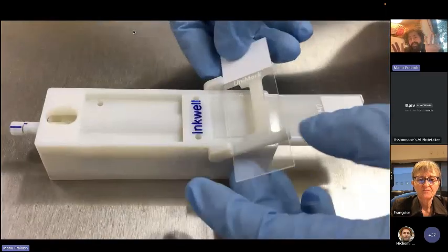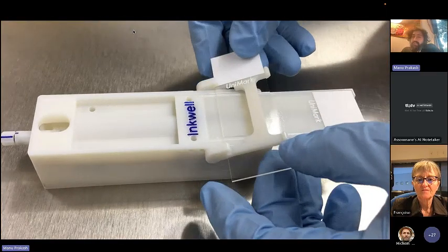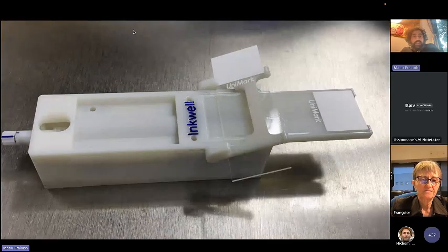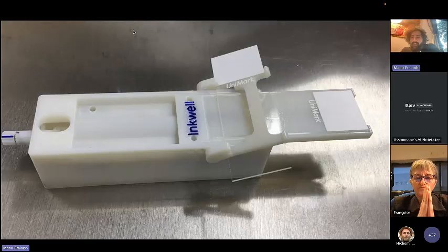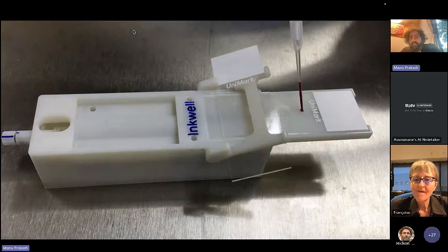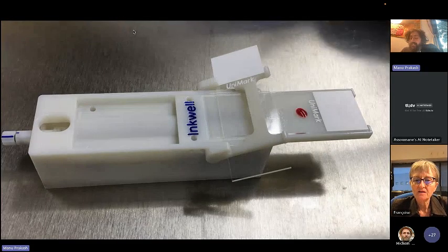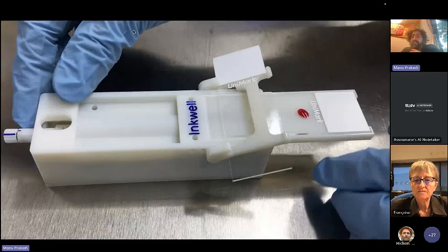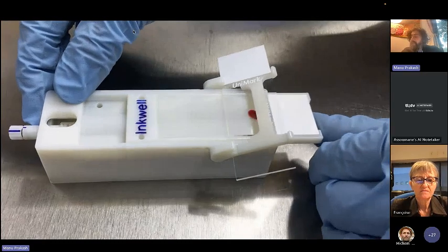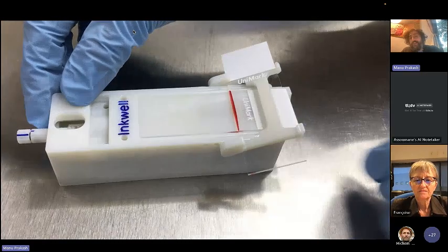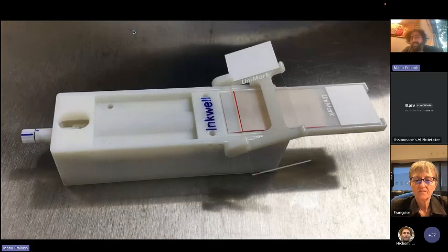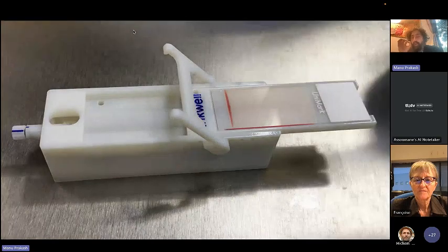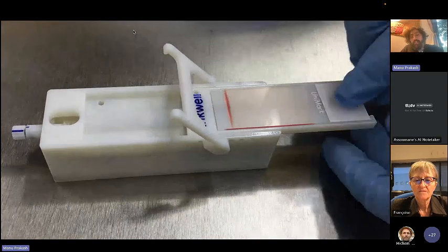It has no batteries, no electricity, just a spring, a syringe, and a valve from a bicycle to regulate the speed. And you'll see the device is able to make perfect smears every single time. We have tested this for tens of thousands of cycles, and it's using the mathematical equation that I had described before for an optimal angle and optimal velocity.